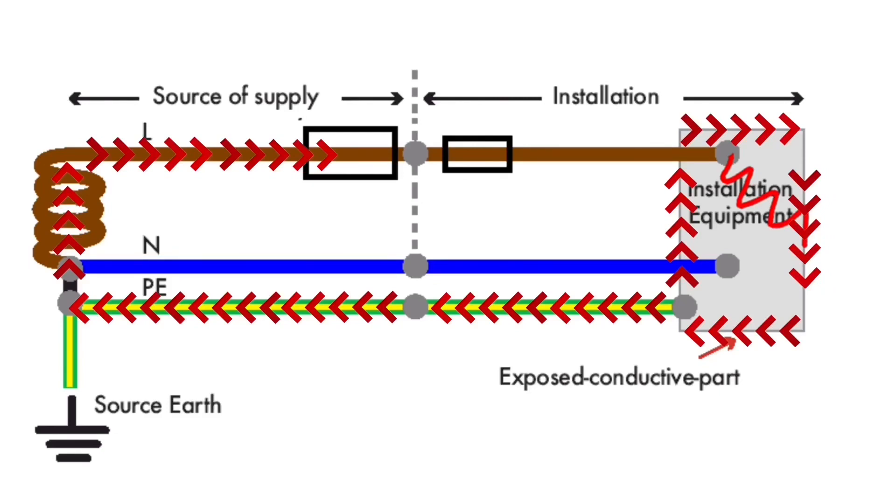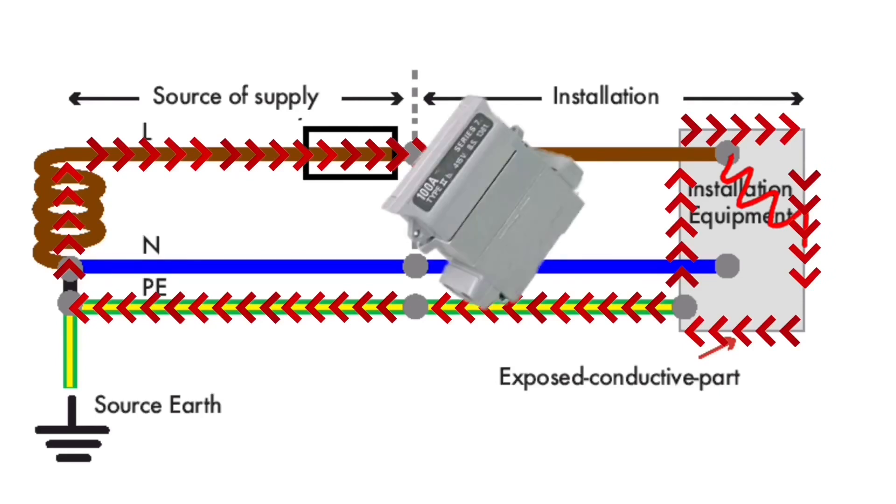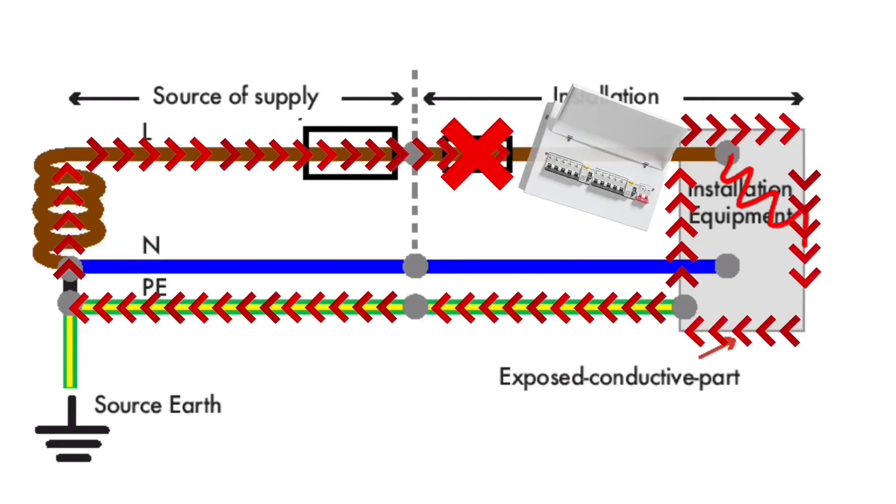The fault current will pass through the main cutout fuse rated at either 100, 80, or 60 amps but will not cause operation. The fuse that will operate is the one closest to the fault. In this case, the fuse located within the consumer unit will operate, clearing the fault in circuit.